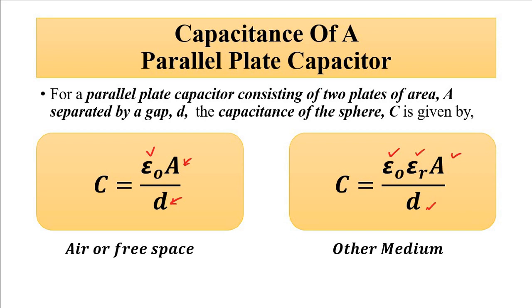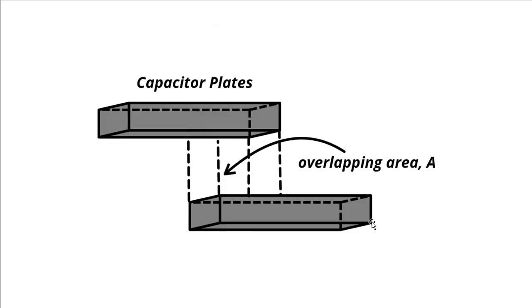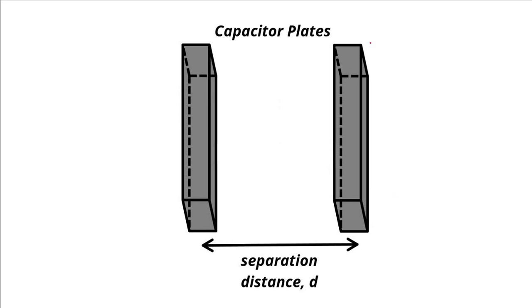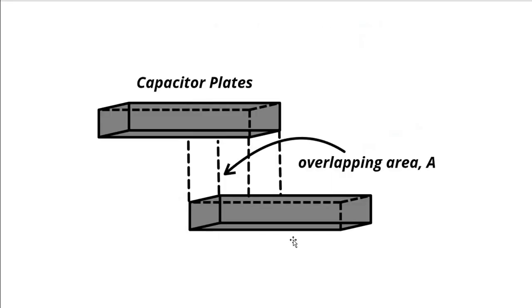For displacement measurement, the two most commonly used parameters are separation distance and overlapping area. One capacitor plate is movable and connected to the object whose displacement is to be measured. When the object moves, the movable plate moves, causing the separation distance to either increase or decrease, producing a change in capacitance. Alternatively, when the overlapping area is used, movement of the object either increases or decreases the overlapping area, also causing a change in capacitance.